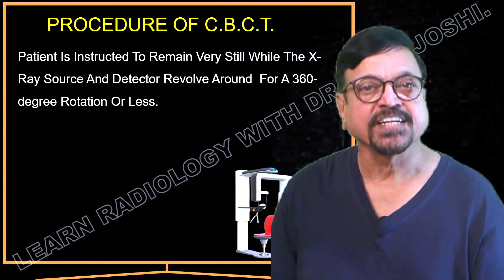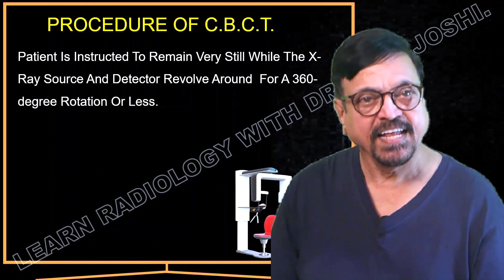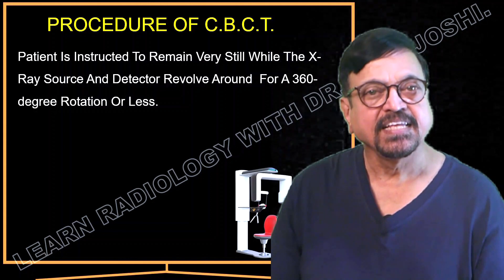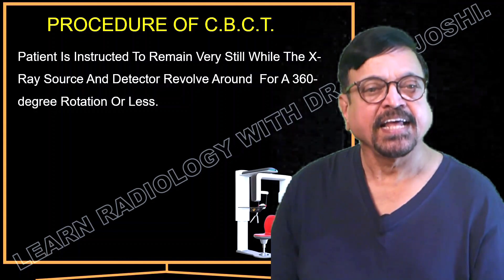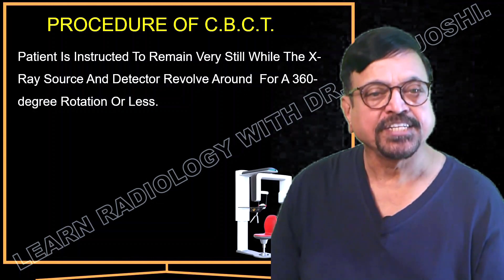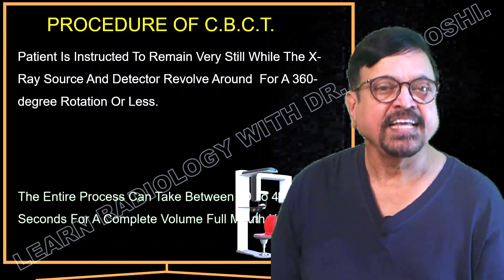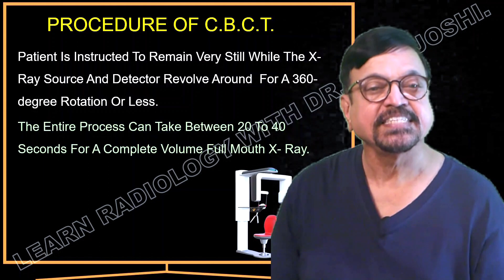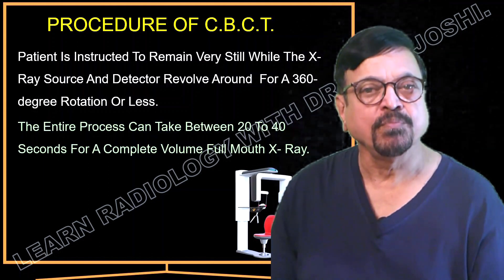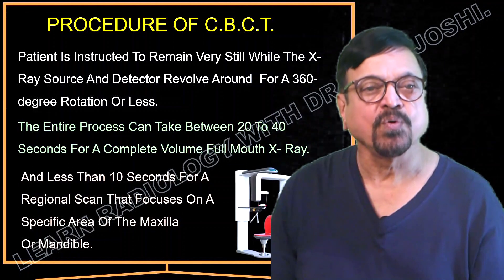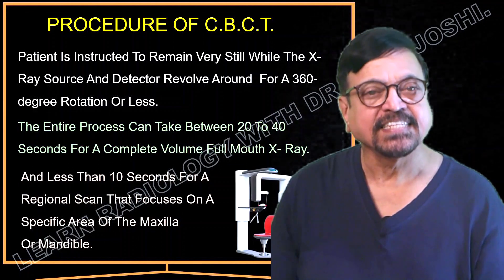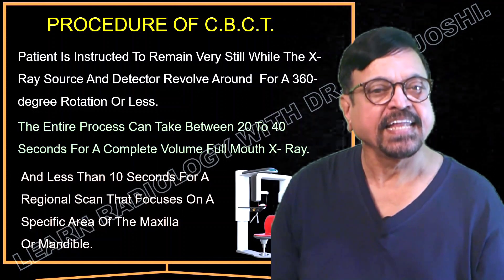The patient is instructed to remain very steady while the X-ray source and detector revolve 360 degrees — or less — making one complete rotation around the patient's head to acquire the data. The entire process can take between 20 to 40 seconds for a complete full-mouth volume X-ray. For a localized or regional scan focused on a small area such as the mandible or maxilla, less than 10 seconds are required.